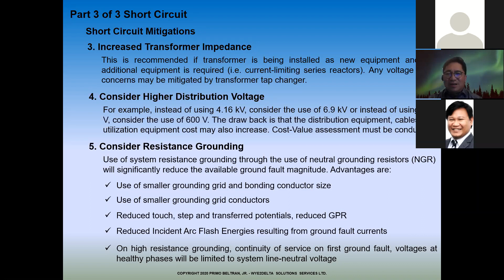The relays will detect it. So on a high resistance grounded system, if one alarms, you know where it is. The NGR relay will alarm as a common alarm in the system, then the operator goes and finds which relay lit up, then isolates it.